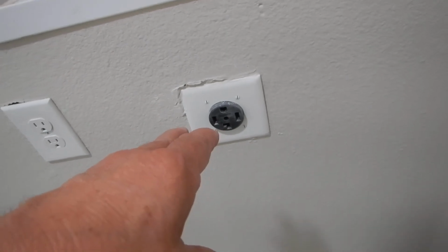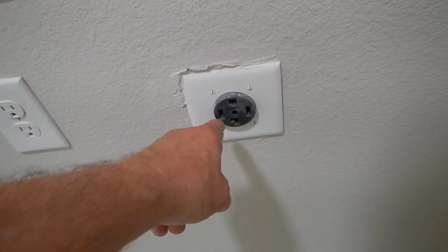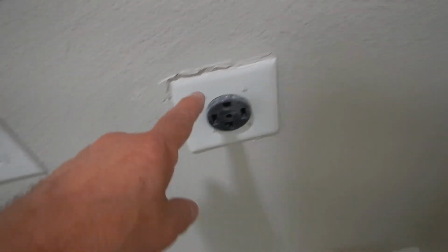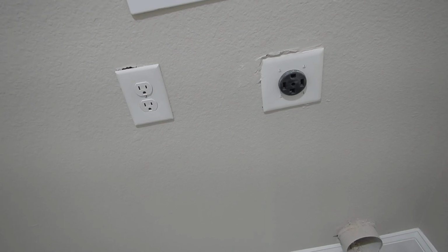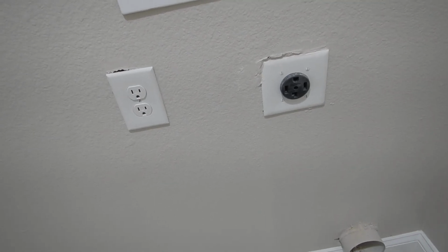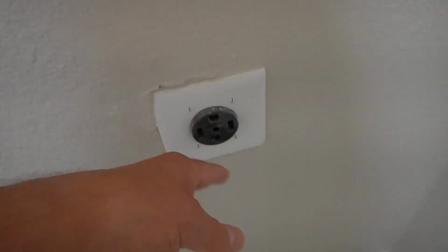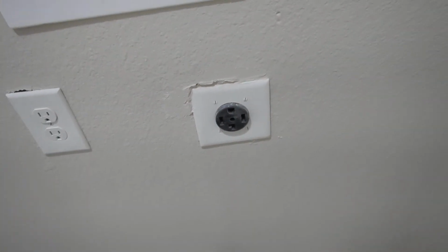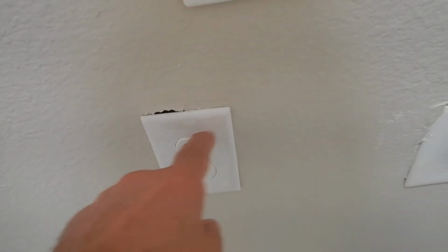All right, this is a 4-prong electric clothes dryer. And I know that I'm getting grounding at these two, and I'm getting 120 and 120 here. I also know that this is sealed in here, and I know this is an older home, and I do not know, I cannot ascertain that one of the grounds is not bootlegged. All I know is that it tests fine. This is GFCI protected, it should have a little GFCI notice.